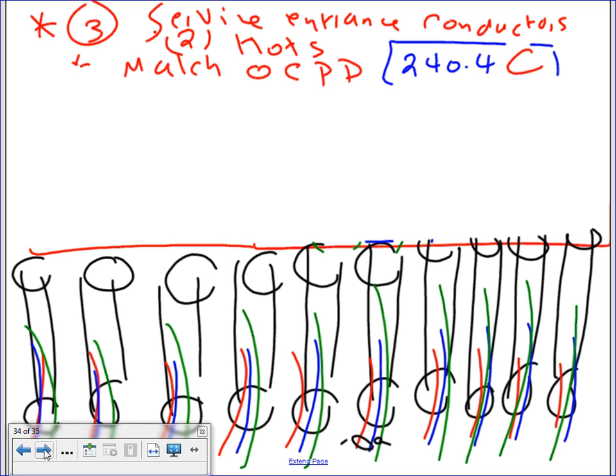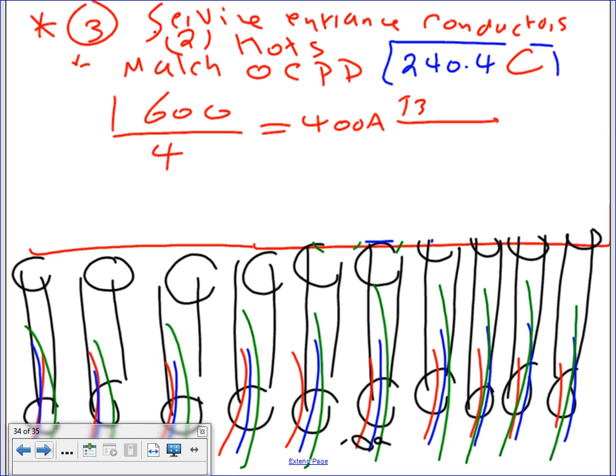I'm not using adjustable, so I'm going to have 1600 divided by 4 because I need to parallel. I have 4 runs, so they give me 4 runs of 400 amps. Take this one to table 310.15(B)(16) under the 75-degree column. That will give me 4 sets. Each one of these sets is 2 conductors, 600 kcmil, THHW.